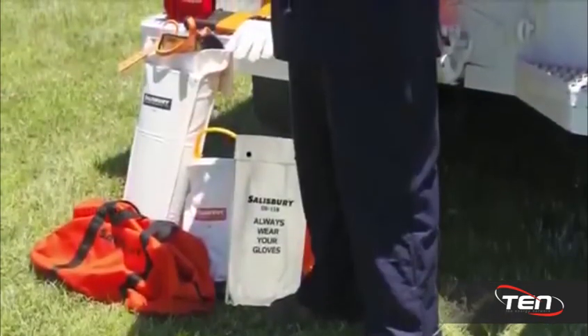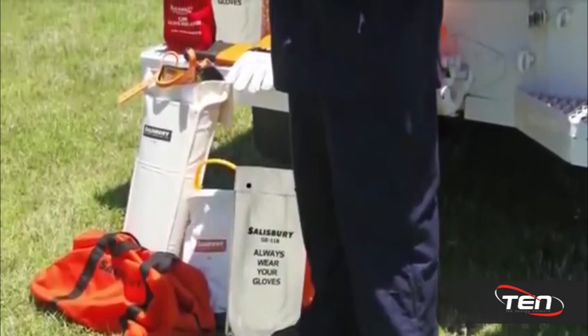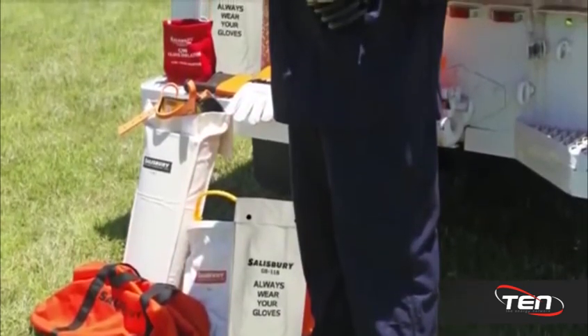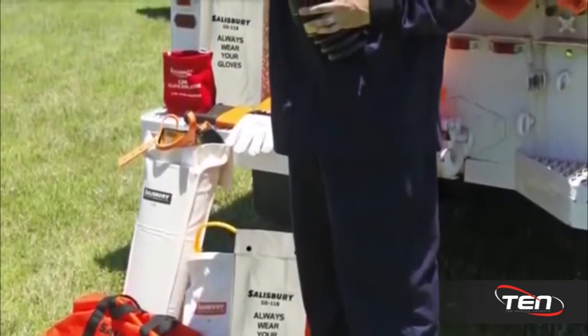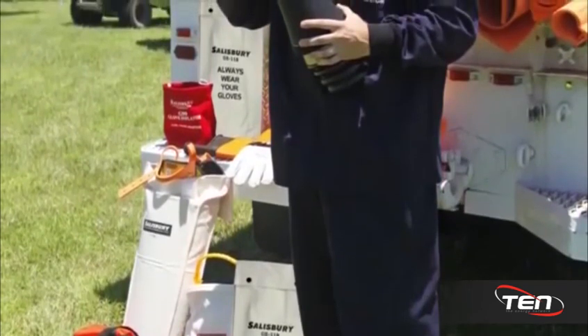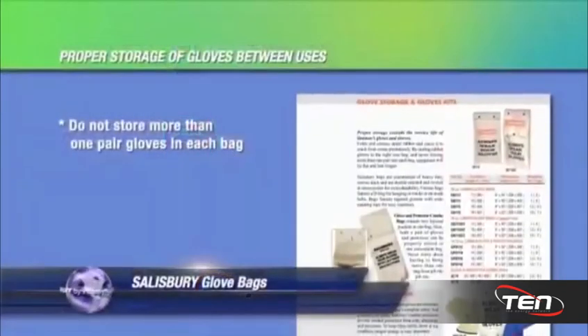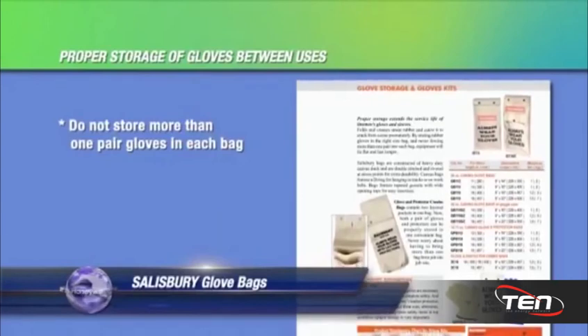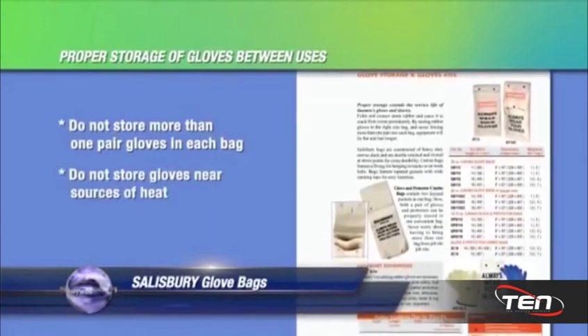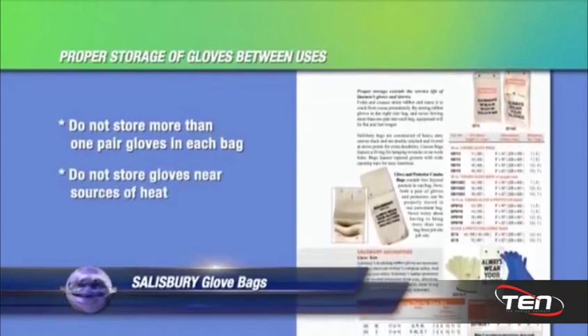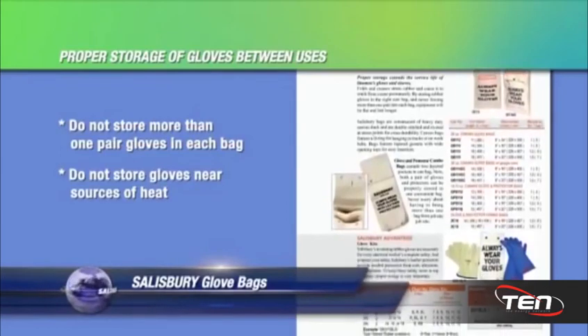Proper storage of the gloves between uses is very important. Rubber gloves should be stored in a glove bag, usually made of canvas, with air holes in the bottom to allow for proper ventilation. Do not store more than one pair of gloves in each bag. Also, do not store gloves near sources of heat, as this can damage the rubber. When putting the gloves in the bag, do not fold them.